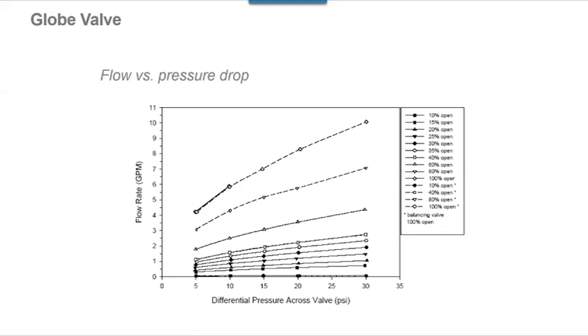The next few slides are testing that was done at the Iowa Energy Center, and Belimo got into the pressure-independent valve business, added pressure-independent valves to our valve line in 2003. And one of the questions that we would get a lot is, are these valves really doing anything? I mean, they look nice, but what are they supposed to be doing? Well, the Iowa Energy Center at the time did some testing between a pressure-dependent valve, a globe valve, which you see on the screen here, and a pressure-independent valve, which you'll see in a couple of slides.